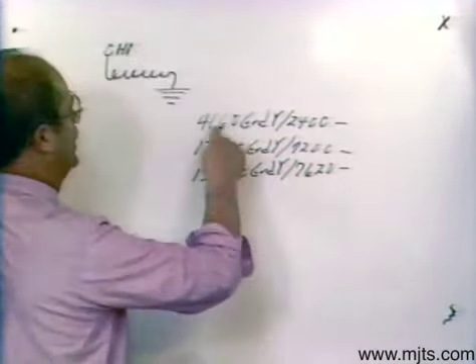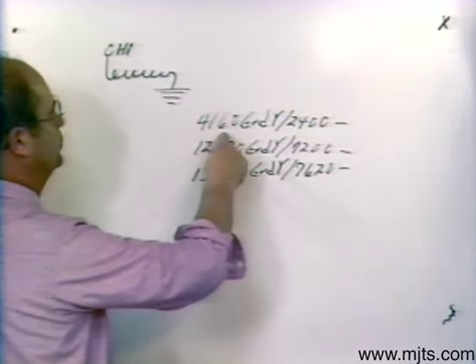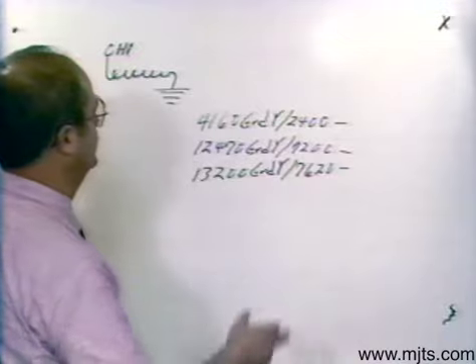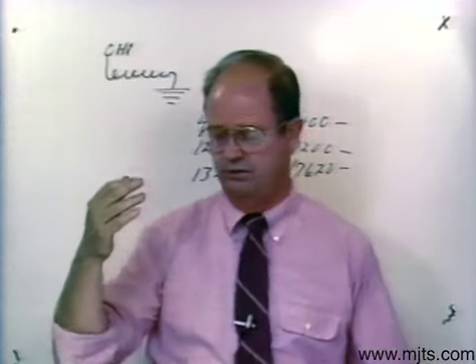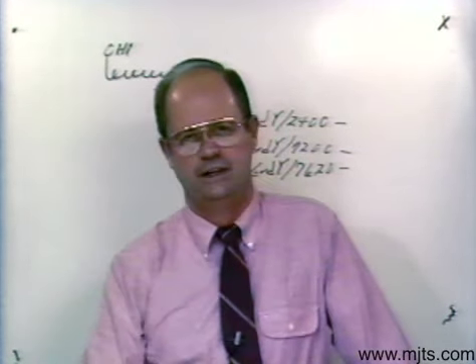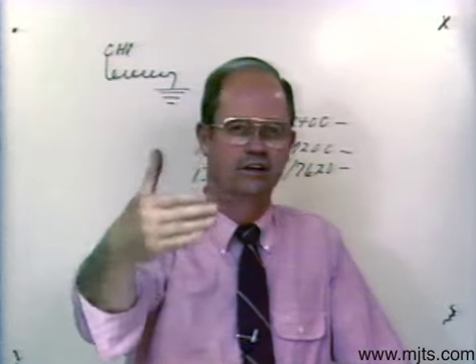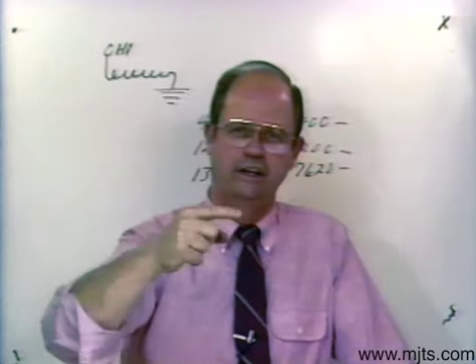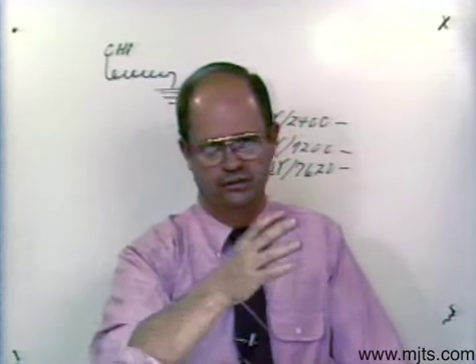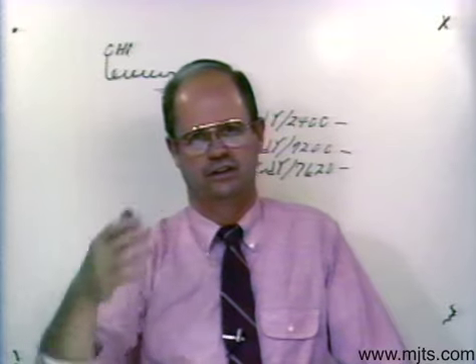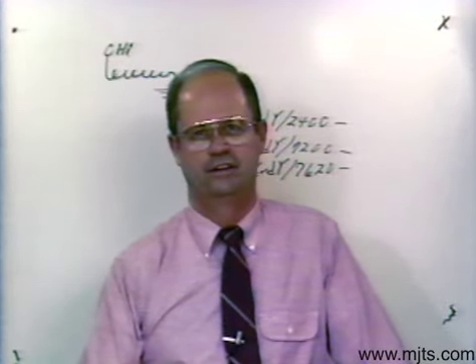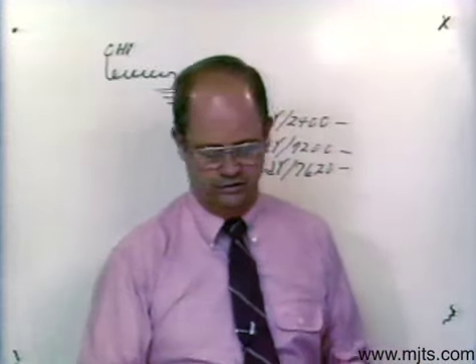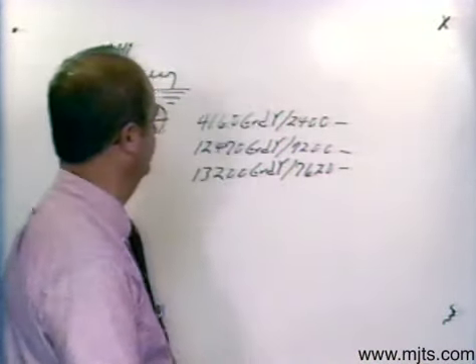If I connect Y on a 4160 system and divide by 1.73, I get a coil voltage of 2400 volts. If you know you're going to use those transformers single phase on a Y system, then why buy the added bushing and added cost? There's another savings as well: as the windings get closer to ground potential, less insulation is needed. Most transformers are connected single phase on rural systems, so they would use a transformer such as this.